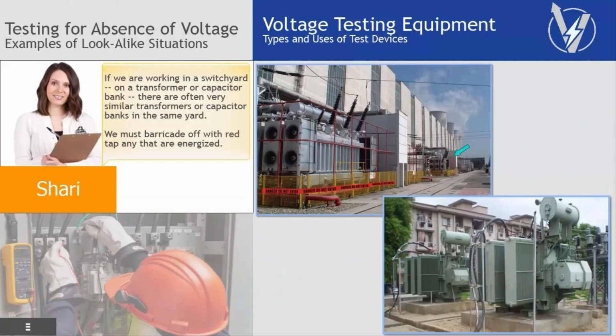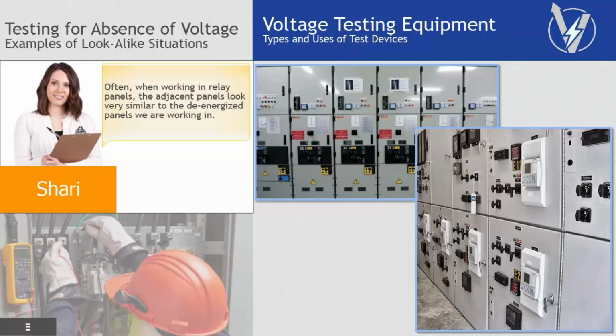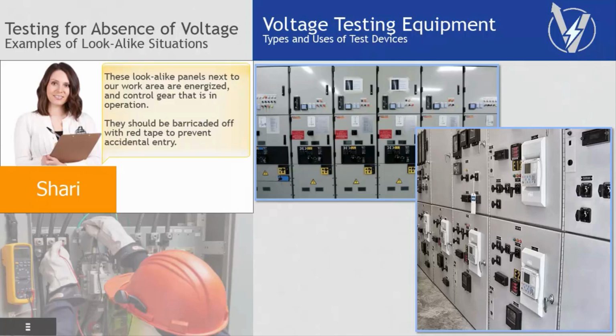If we are working in a switchyard on a transformer or capacitor bank, there are often very similar transformers or capacitor banks in the same yard. We must barricade off with red tape any that are energized. Often, when working in relay panels, the adjacent panels look very similar to the de-energized panels we are working in. These look-alike panels next to our work area are energized and control gear that is in operation. They should be barricaded off with red tape to prevent accidental entry.